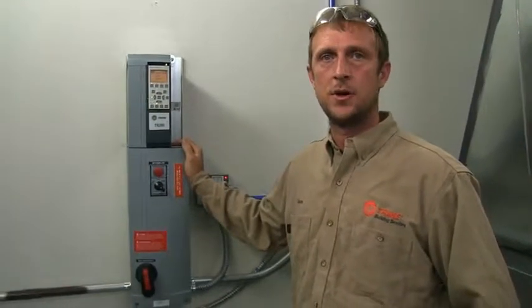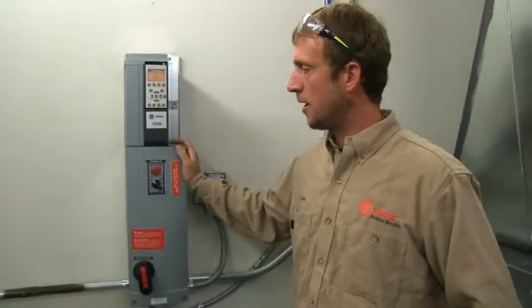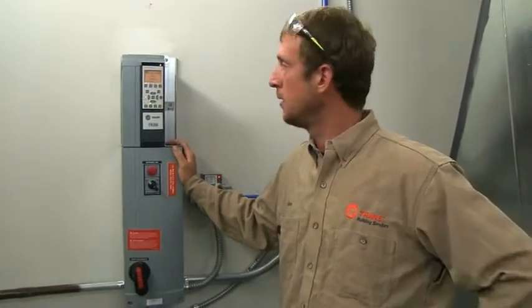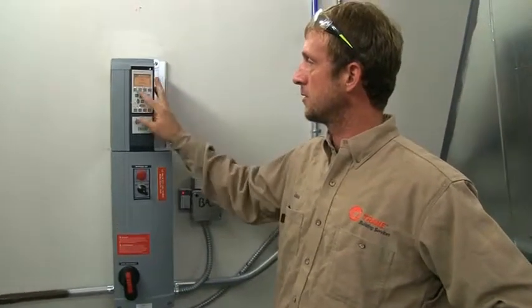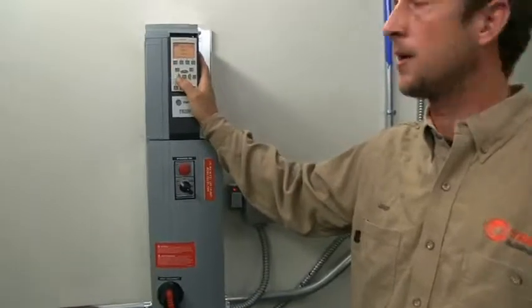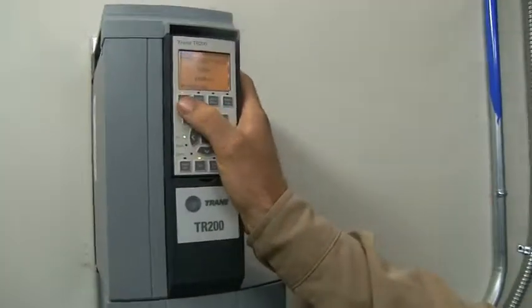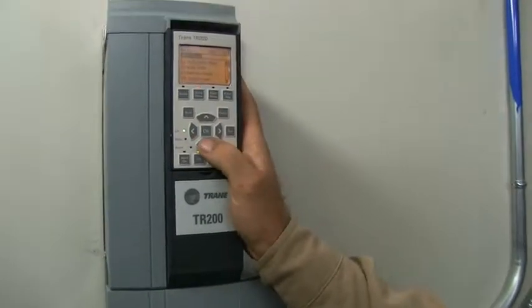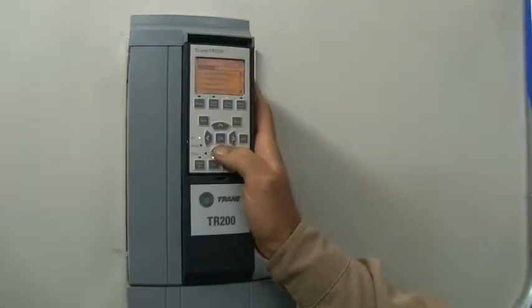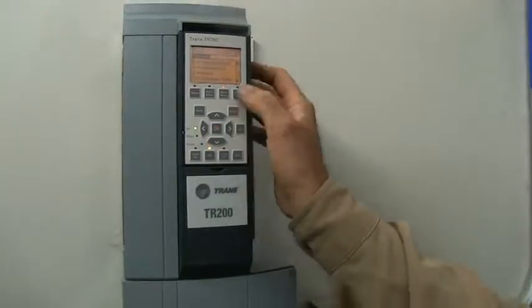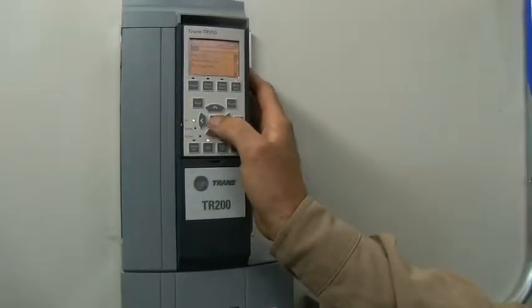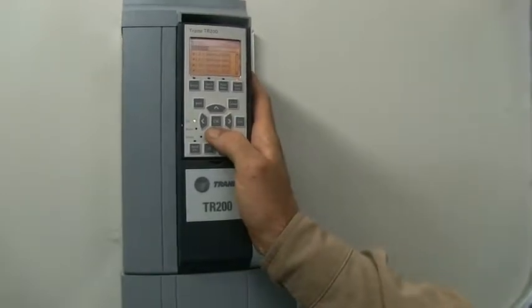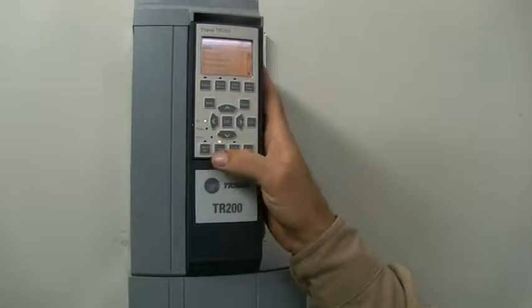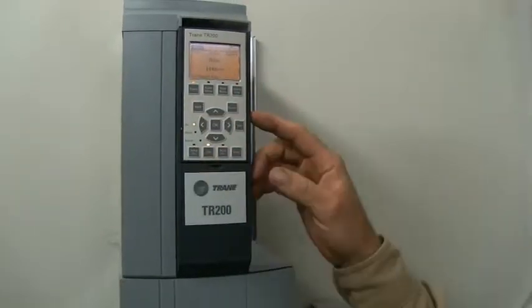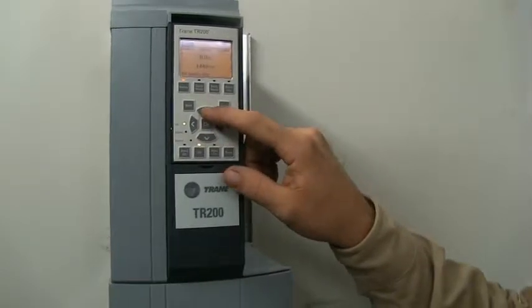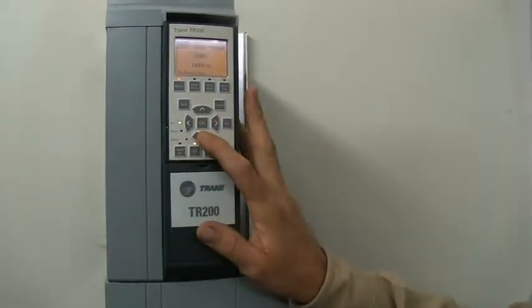It's a Trane TR200 variable frequency drive. This drive is controlling the air handler motor. Pretty much, there's a set of buttons across the top and a set of buttons across the bottom. The top buttons are how you get your status, quick menu for parameter setups, main menu for more extensive parameter setups, and then of course alarm log up in the top right hand corner, which tells you all the historic alarms that the drive has had. Up and down arrows cycle through the different settings for display.